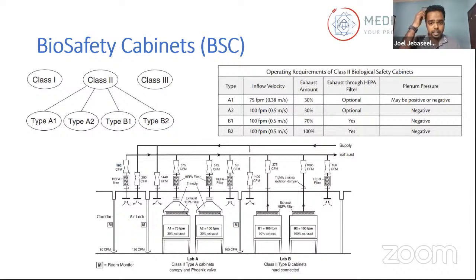And a lot of these cabinets are made to protect both the users as well as the product, right? So this is not similar to a laminar hood cabinet. A laminar hood cabinet only helps to protect the product, and the principles are different, right? So the positive and negative pressure plays a part. Whereas biosafety cabinets always protect both the users when you're using those cabinets and the product that you're installing or operating inside the cabinets. One other important thing is the sash opening, right? So how much should it be open? That also plays a big criterion.